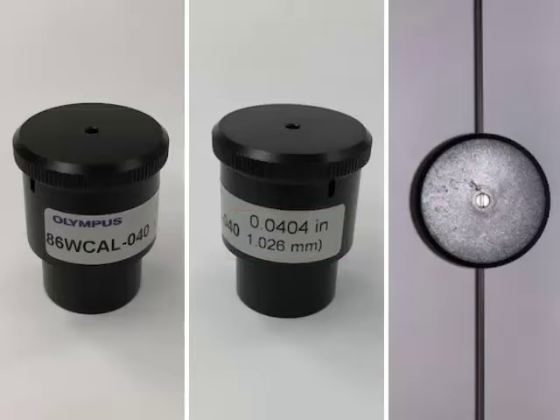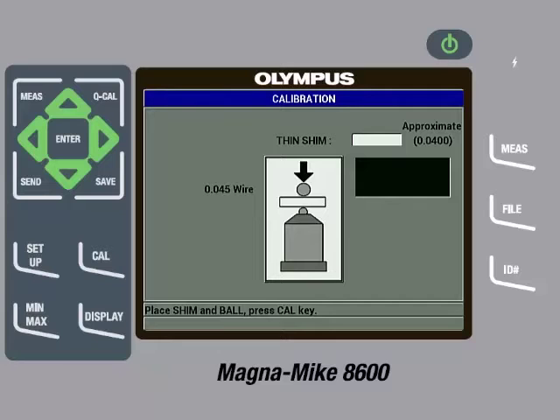We will then unscrew the top cap enough to allow for the wire to be slid through the slot on the side of the fixture. Make sure that the wire is on top of the shim so that when it is placed on the probe, the shim is between the wire and the probe tip. Then, screw the top cap down enough so it is secure and the wire is aligned properly. Then place the wire and calibration fixture on the probe and gently pull down on the sides of the fixture to make sure the probe tip is in contact with the shim. The instrument will start displaying a thickness value. Once the reading is steady, press the cal key.